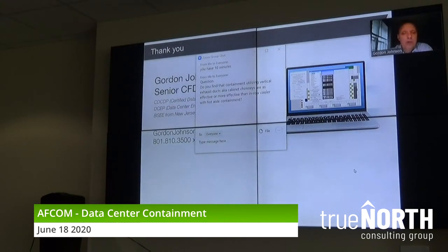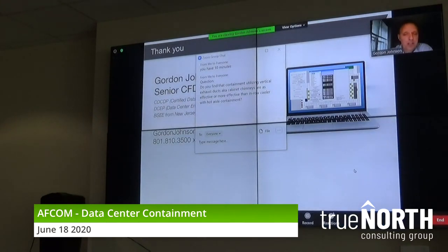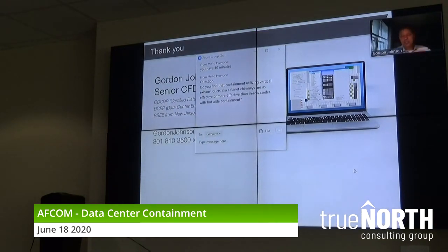If you had one or two racks with a very high density, and you wanted to make sure you push that air up, maybe to a drop ceiling or as high as possible, without that hot exhaust air coming out and affecting the neighboring cabinets or rolling over to other portions of the data center, that would be an example of where I could go with one or two cabinet chimneys.